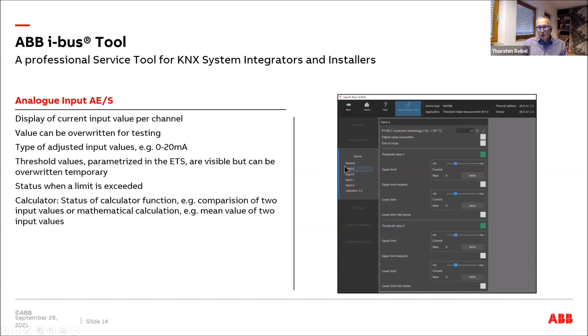For the analog input — a four-channel device with pages for inputs A through D — you can see the input value, change threshold values, and overwrite the actual input value for test purposes. If you overshoot the threshold, you can observe the real action behind it. Additional pages cover status information and internal calculations such as comparison of two input values or mean value computation.